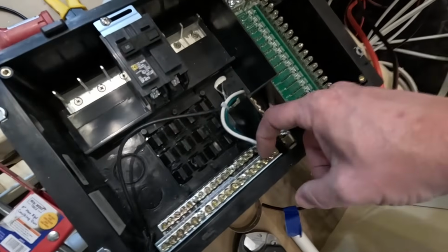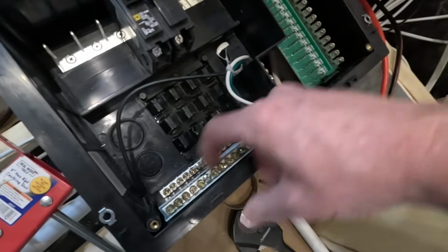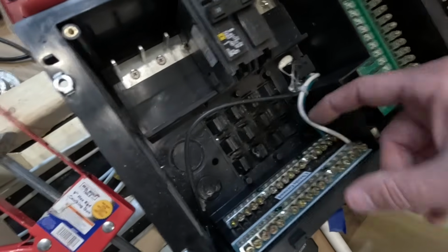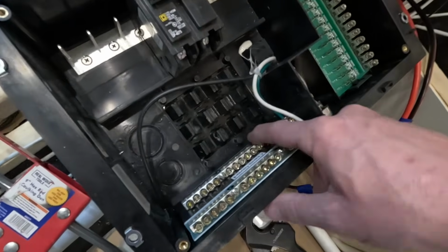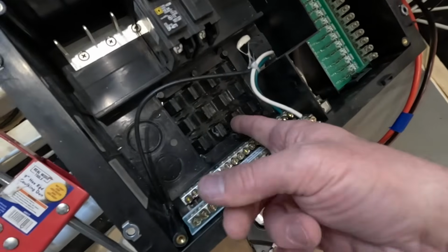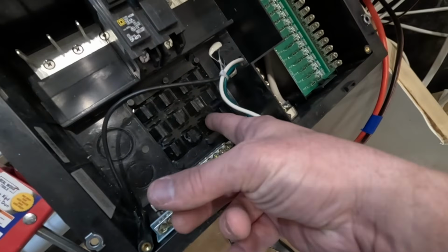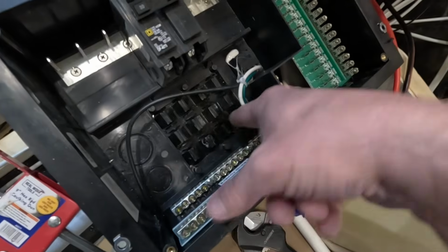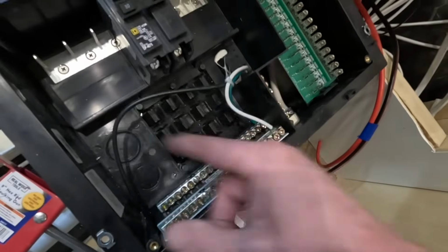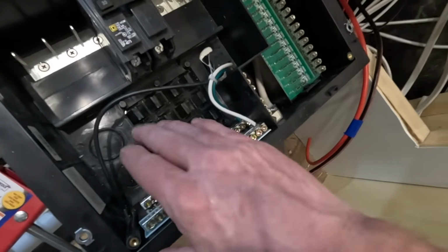We'll wire our neutral line coming in into this bar here, and you see our green wire back here - this will be for our ground bar. All of our circuits will go out through these holes here in the back and come in to wire to their respective breakers, neutral and ground.